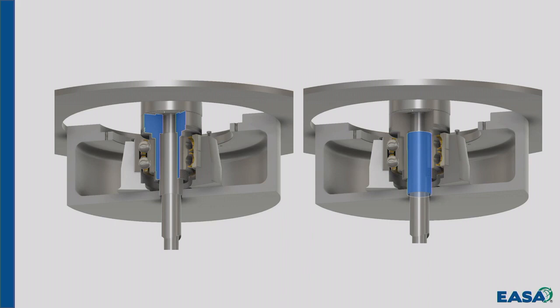Okay? This is the carrier that has the bearing on it. It's turning. Right inside of here is the stand tube. So the stand tube is inside of the carrier, which is spinning. Okay? And the pump shaft is inside of the stand tube. So the stand tube is stationary, this is turning inside, and that is turning outside. So you've got a situation like this. Okay? And it's filled with oil up pretty close to the top when it's running.